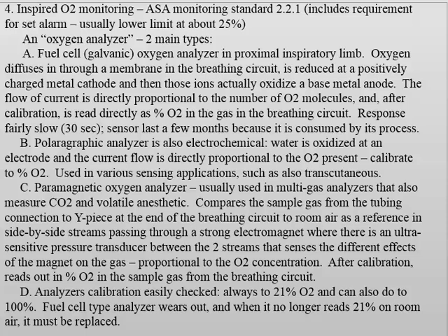And the flow of electric current, as it says there, is directly proportional to the number of oxygen molecules, and once it's calibrated, usually to 0, 21, and 100, or as close to 100 as you can get, then the monitor will read the percent of inspired oxygen. It's relatively slow, and the sensor does get consumed and has to be changed, but this is the classic inspired oxygen monitor.